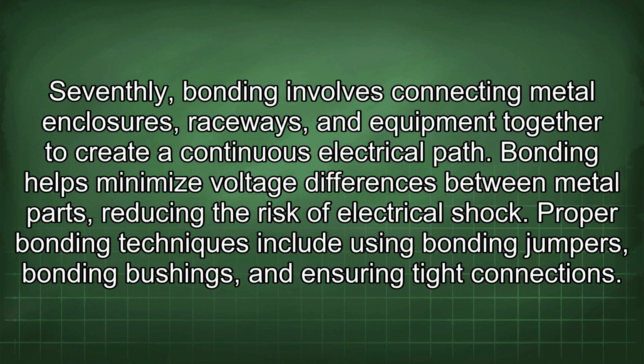Seventhly, bonding involves connecting metal enclosures, raceways, and equipment together to create a continuous electrical path. Bonding helps minimize voltage differences between metal parts, reducing the risk of electrical shock. Proper bonding techniques include using bonding jumpers, bonding bushings, and ensuring tight connections.